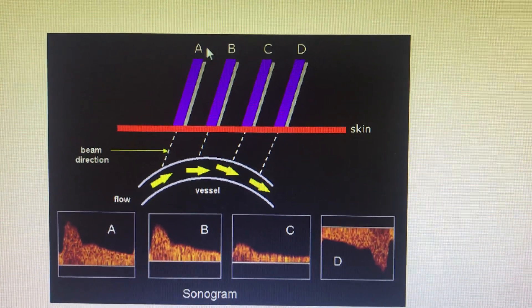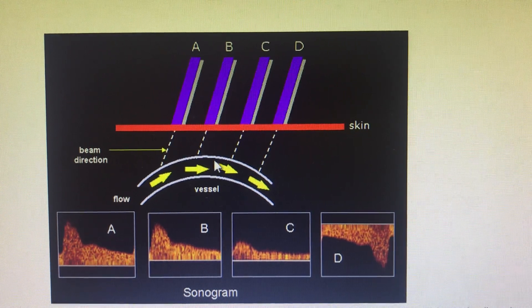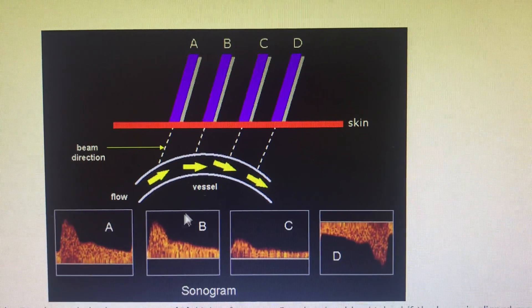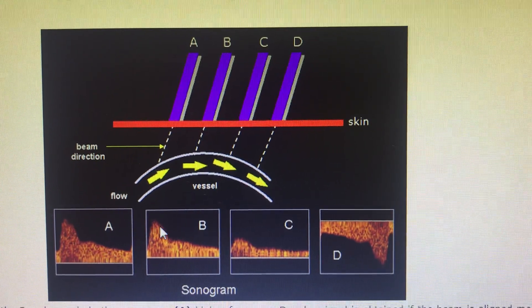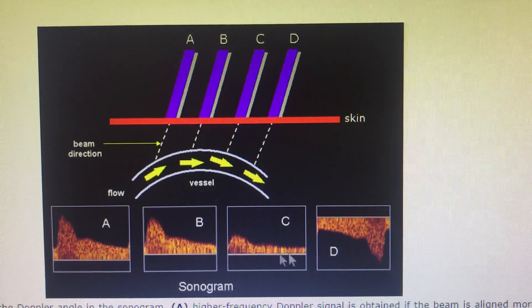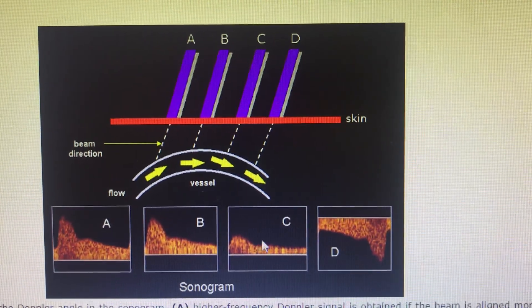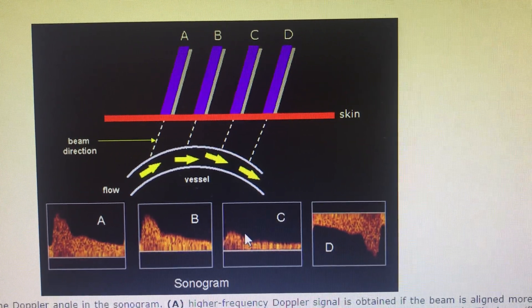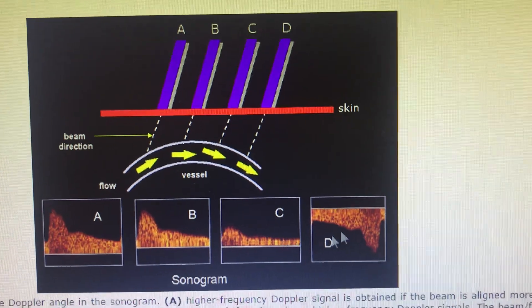At probe position B, the angle is almost 75 to 80 degrees, and usually that amplitude will be nullified and decreasing. If you see position C, it's almost neutral - absolutely 90 degrees - so the amplitude or velocity is almost negligible.